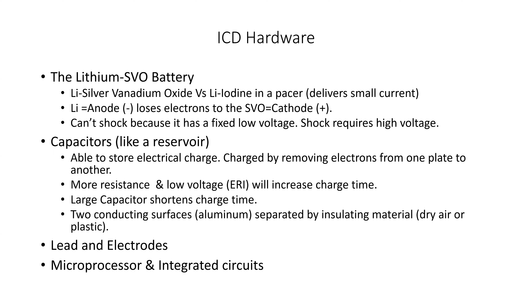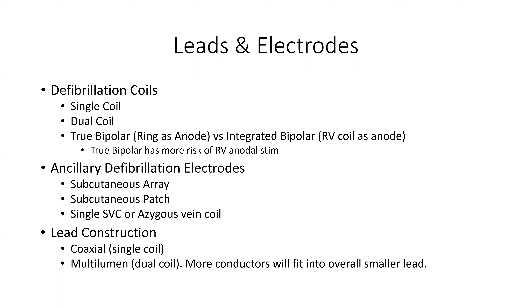With ICDs, we have two types of leads. You can have a single coil or a dual coil. For people who do extraction, they don't like the dual coil because it adheres more to the SVC. Then you've got true bipolar versus integrated bipolar. Integrated bipolar is a way where companies try to make the synthesis of the lead more simple, where there's no ring, but they use the distal coil as a ring. That could have a benefit, but it also has some downfalls, as we will see on the next slide. And then we have ancillary defibrillation electrodes if needed, like a subcutaneous array or a subcutaneous patch. The lead construction could be coaxial versus multilumen. Multilumen we see more in a dual coil system.